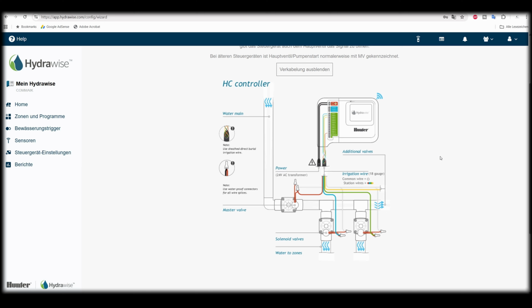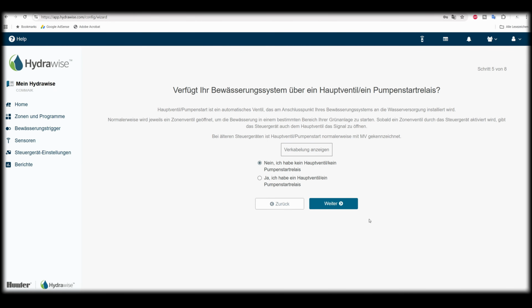Important: the controller only provides a 24-volt AC control signal. The relay must not switch a 230-volt load directly. The appropriate wiring diagram is displayed in the HydraWise Assistant and helps ensure correct connection.